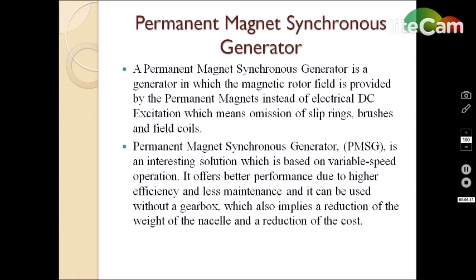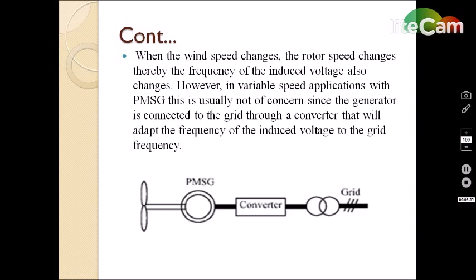We know that when the wind speed changes, the rotor speed also changes, so the frequency of the induced voltage also changes. But the grid has a fixed constant frequency, so using an ordinary induction generator is not very worthwhile. In PMSG, it is connected to the grid through a converter, which adapts the frequency of the induced voltage to the grid frequency. So there are no frequency problems when we use PMSG along with converters.